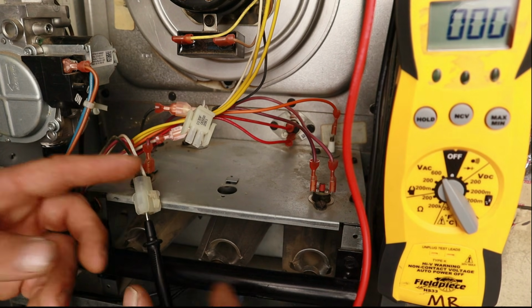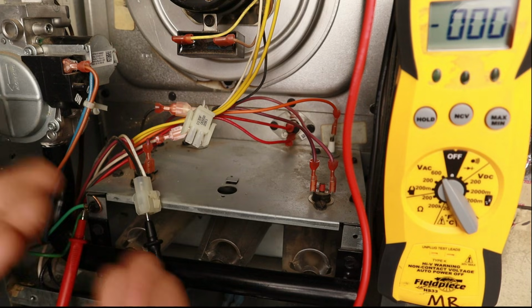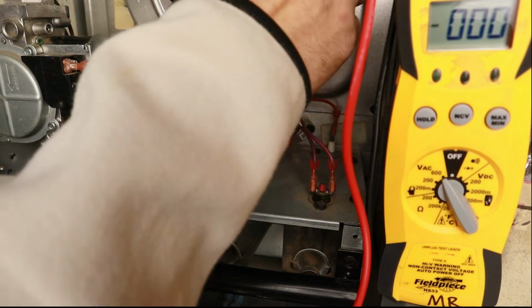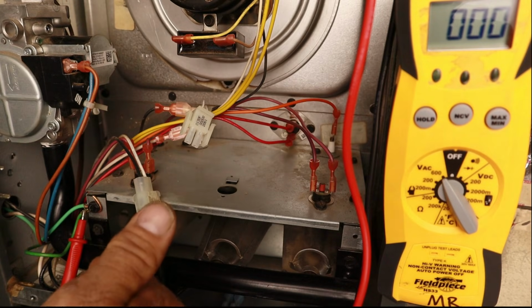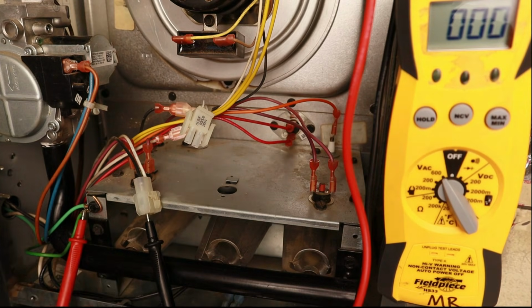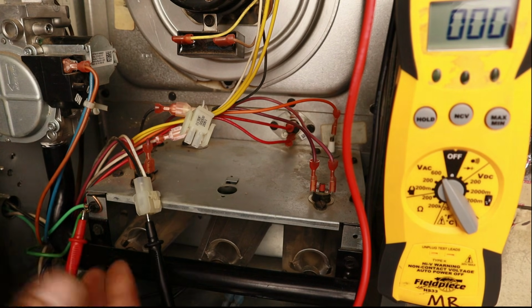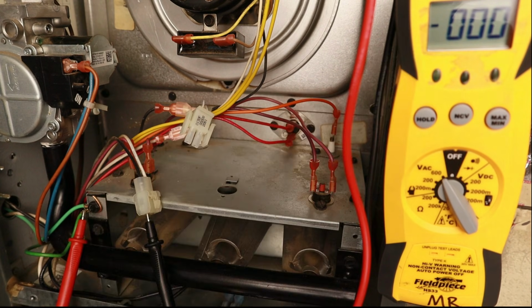So what I'm going to do now is wait for the time delay on the thermostat to pass. Our inducer motor will start, our pressure switch will prove, and the 24 volts that the control board sends out to the pressure switch will travel through because that switch will close. The 24 volts will go back to the control board. That tells the control board everything's okay and it can move on to the hot surface igniter. And at that point, we should start reading our voltage.